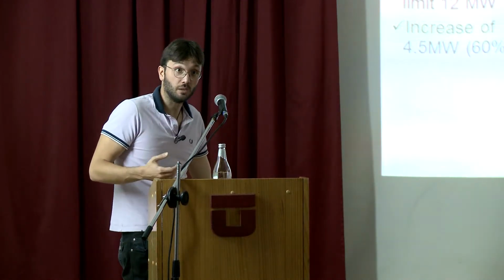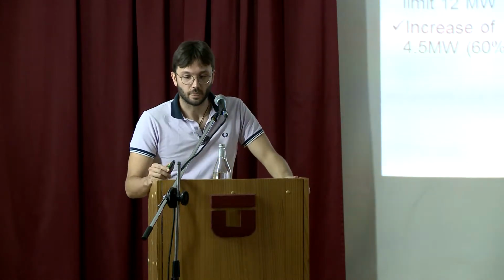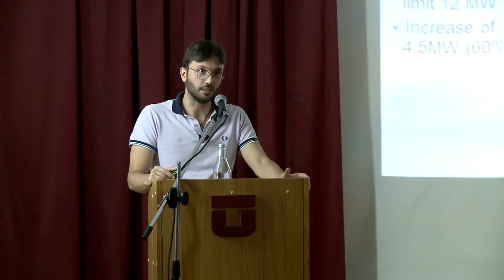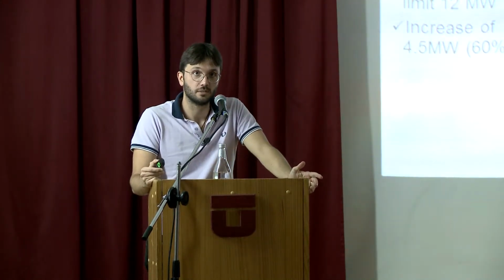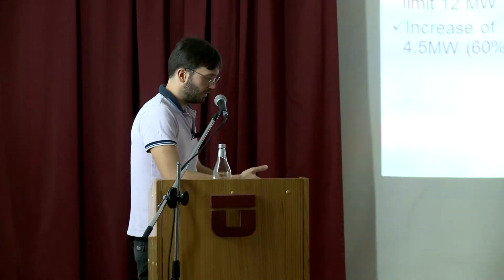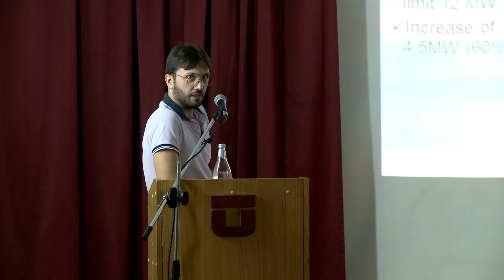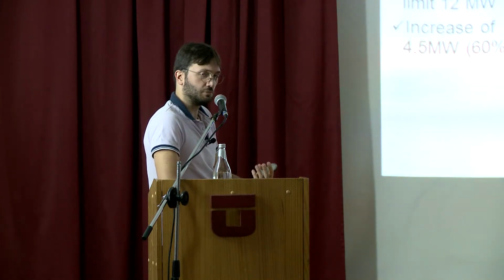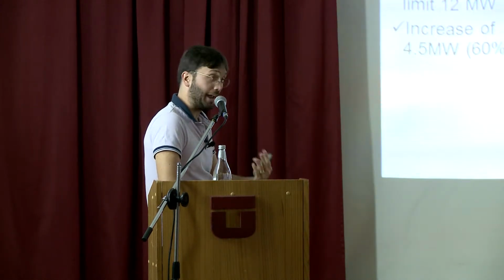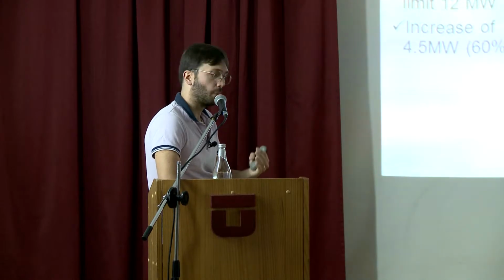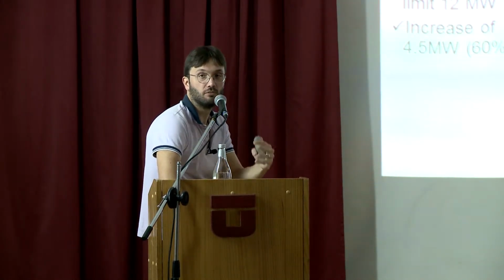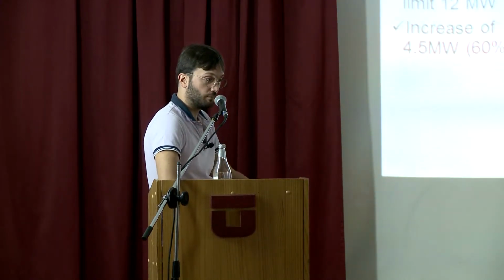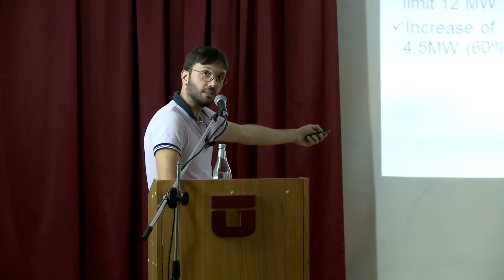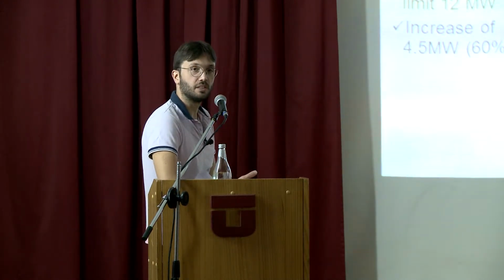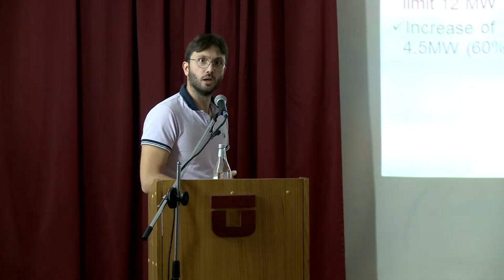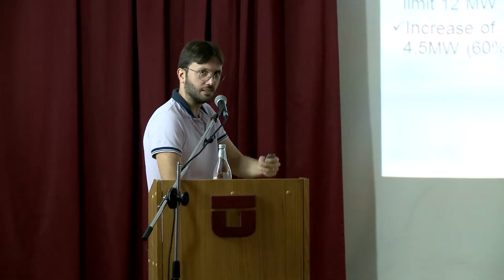Increase of 60% of wind power. So it's massive. It means that in that line, I can have 60% more wind power just by doing this little thing. So there is really a lot of margin. It means two things: yes, the smart transformer is working, and second, the actual infrastructure is not being used in the optimal way. So there is a very big margin of improvement. Anything is good, because if with something this easy as a droop control we increase penetration by 60%, then it means that we can really do a lot. We see the light at the end of the tunnel.